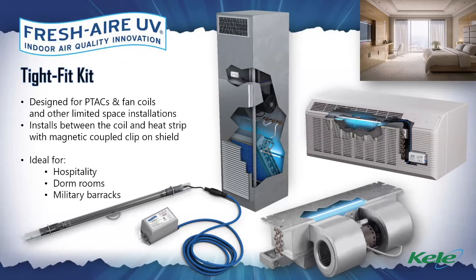So our tight fit unit is a small UV lamp with a magnet mount, very, very refined, easy to install, easy to slip into those very small tight spaces, great for terminal fan coil units and PTACs. And it does a great job of addressing the coil, the biological blow off, the microbial contamination that gets reintroduced into the room, as well as disinfecting the air on a continual basis.